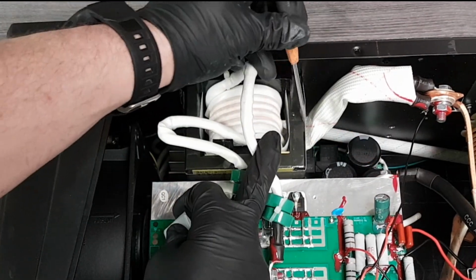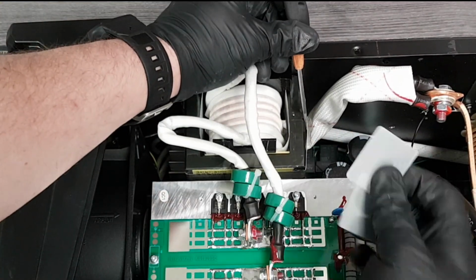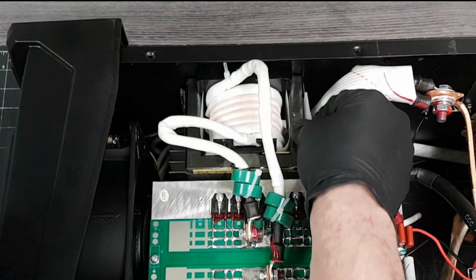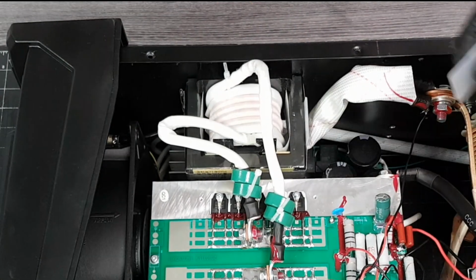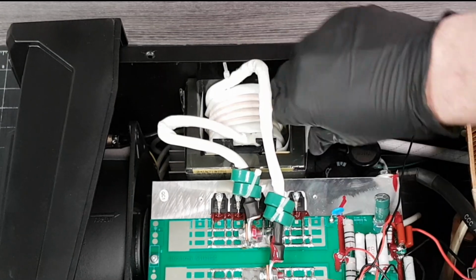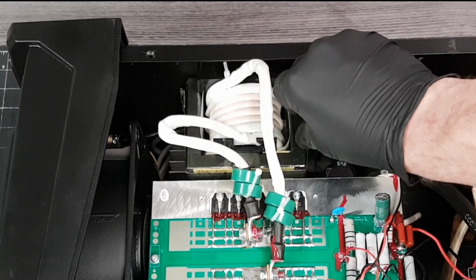This problem can be easily resolved by wedging a non-conductive material between the strap and the transformer. When I need to wedge a transformer, I'll start by using a small screwdriver to open up the strap enough so I can fit my first wedge in. Then I'll push my second wedge in behind the first.